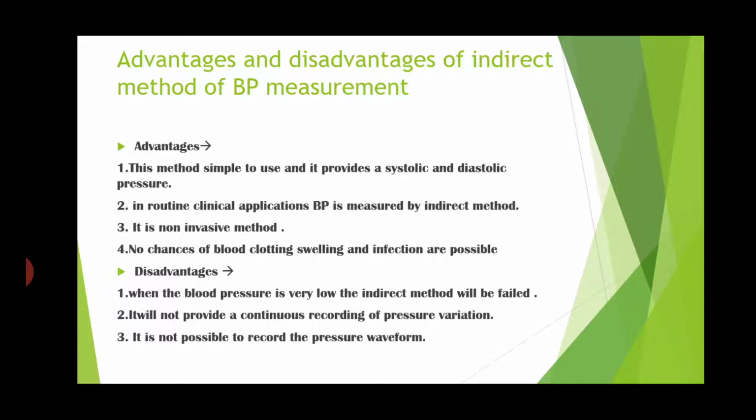In routine clinical application, BP is measured by the indirect method only. It is a non-invasive method. No chances of blood clotting, swelling and infection are possible in this method. Disadvantages. When the blood pressure is very low, the indirect method will fail. It will not provide a continuous recording of pressure variation. It is not possible to record the pressure waveform. These are the disadvantages of indirect BP measurement.